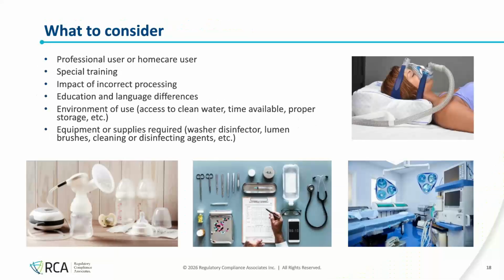Something that's really important to remember with this is that reprocessing steps are validated under their own submission. So under a 510(k) submission to the FDA, you do your reprocessing steps, you submit those, and you show that you prove those steps worked. And that's all good, but if you don't connect that with the user being able to do it correctly, you kind of void that assurance.